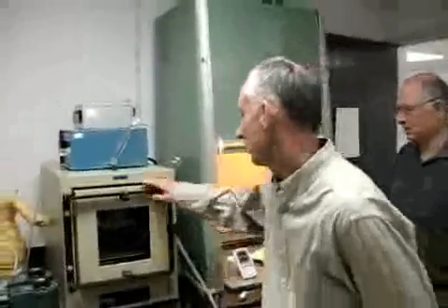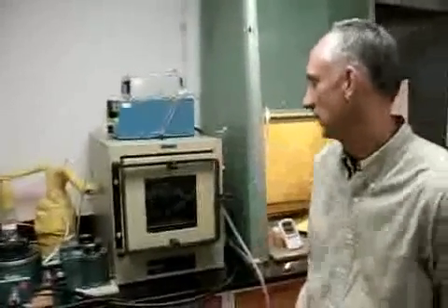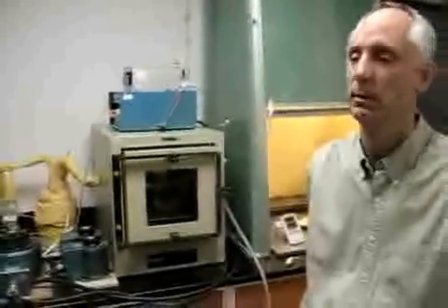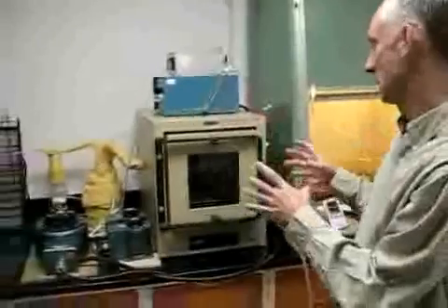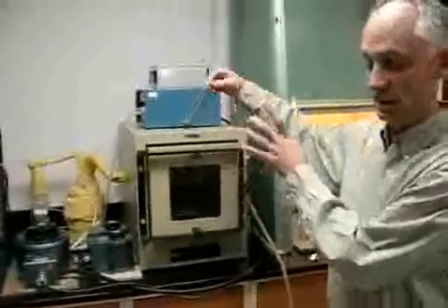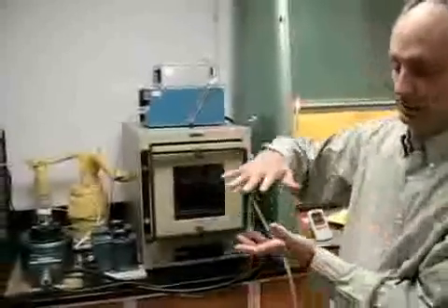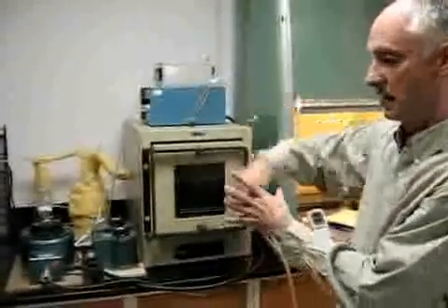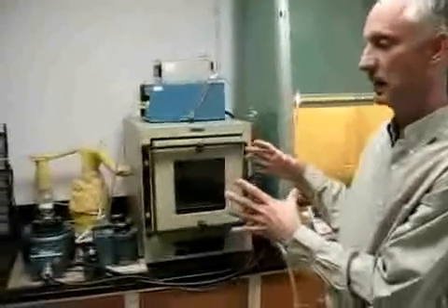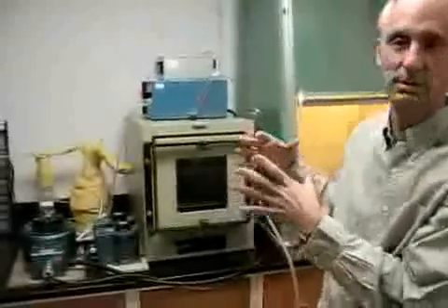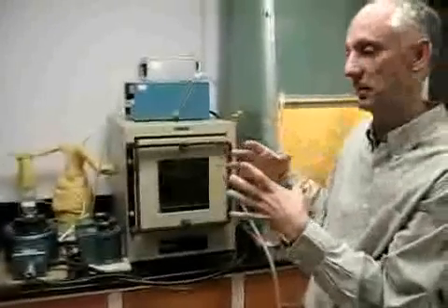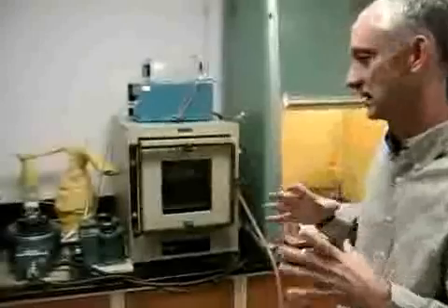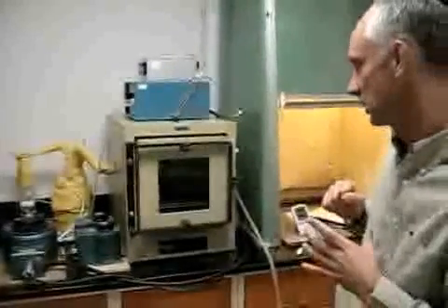Okay, what we have is an incubator that we're temperature controlling to a temperature of 52 degrees C with a tolerance of plus or minus 2 degrees C, both in variation in time and space within the oven. We verified this by measuring air temperature in various locations, and a surrogate of samples, we used fairly coarse sand, placed thermocouples in that, and those are actually far less variable in temperature during time than the air is, as you would expect, because of the thermal mass of them. So the samples are going to be more stable even than the air in terms of temperature fluctuation.